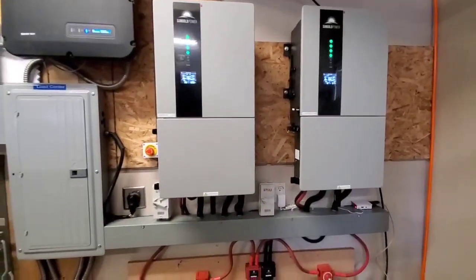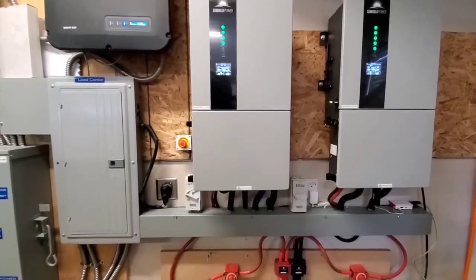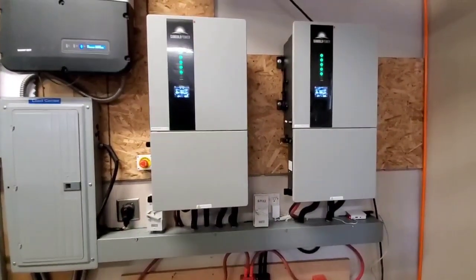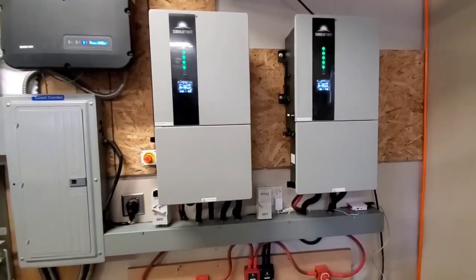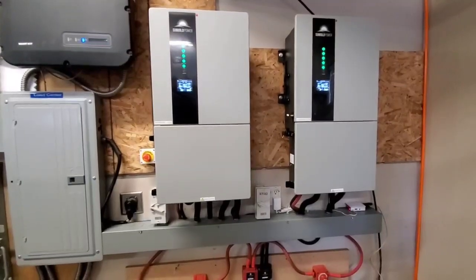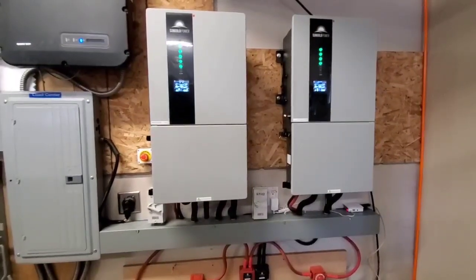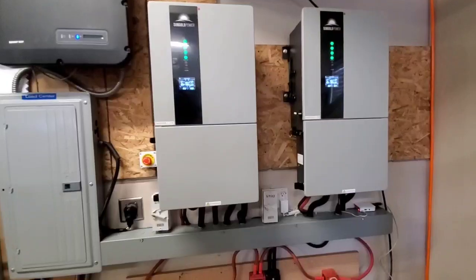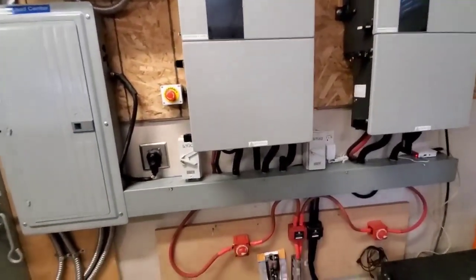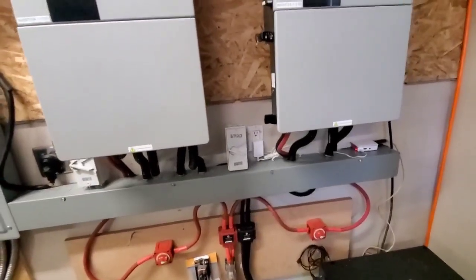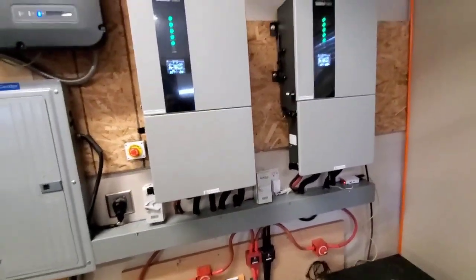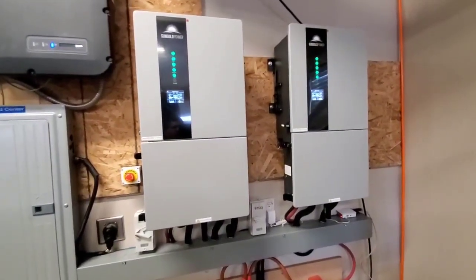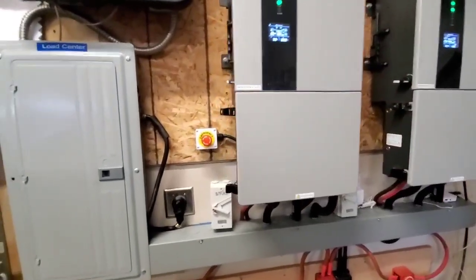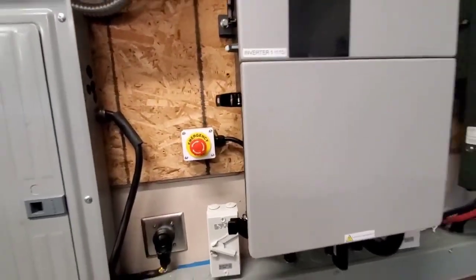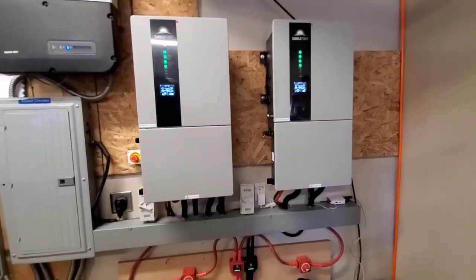I have this wire tray that goes in. That's a load center, with main circuit breakers on the other side of the wall here. I have two breakers, 60 amps, one to go to each inverter, and then I have disconnect switches to power off each one from here instead of going back to the breaker box. I also installed an emergency switch so if something goes wrong they can power it down quickly.